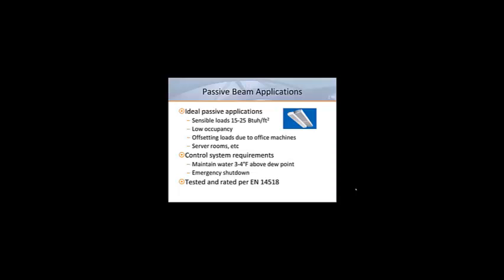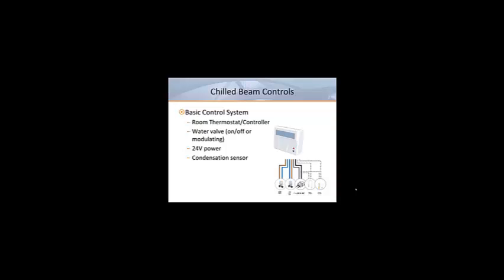Now let's take a look at the controls required to operate chilled beams. Each zone will require a thermostat or room controller with a room temperature sensor. It will be powered by 24 volts AC. This controller will have output capability to operate water valves to control cooling and or heating in the case of an active beam. The valves could either be two position on-off valves or 0 to 10 volt DC modulating valves. While on-off valves should be adequate for the purpose of controlling chilled beams, it is best if they open and close slowly.